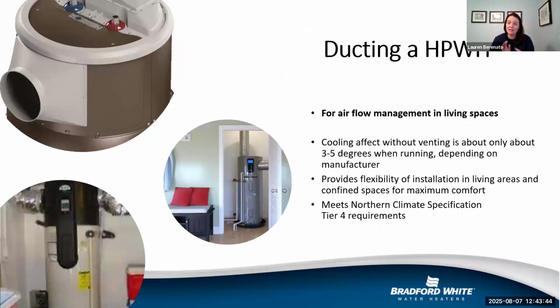So for ducting, this is a nice feature. Most manufacturers do have ducting kits available for heat pump water heaters. I mentioned the 3 to 5 degree temperature drop. With ducting, you can pull the air from outside, or put the air elsewhere, internally or externally, which is a nice feature.